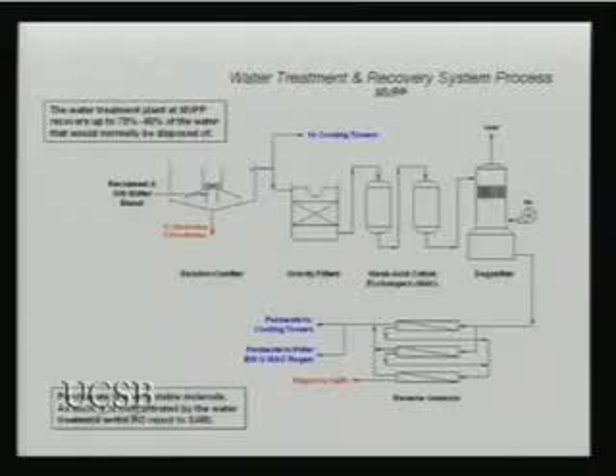We go to weak acid cation exchangers, sometimes known as ion exchangers, water softeners. It's an acid cycle water softening process. All the hardness gets removed, exchanged for hydrogen ions. The water gets very carbonaceous. It goes into what is known as a degasifier, just an air stripper. CO2 comes off, and then it goes into the reverse osmosis system. This is a two-stage system. It's also configured as a two-pass system, which is another way of configuring it. But basically, this desalinates the water to a pretty high quality. Some of the water goes back to the cooling towers. Other is used in other parts of the plant. All the wastewater generated here from the weak acid cation exchangers is very acidic and is neutralized, and that goes into the slurry line as well. Now for the pictures. See, this is not going to be so bad after all.